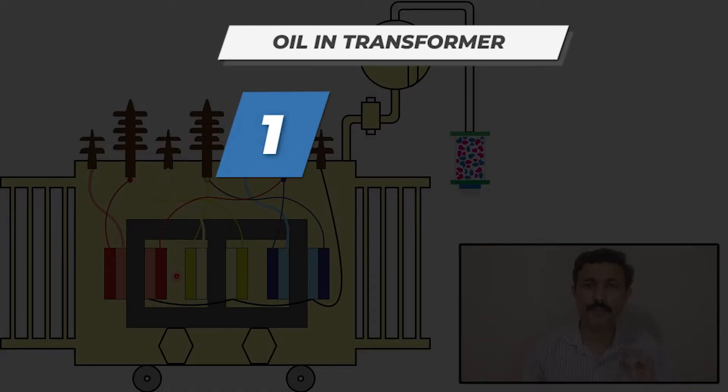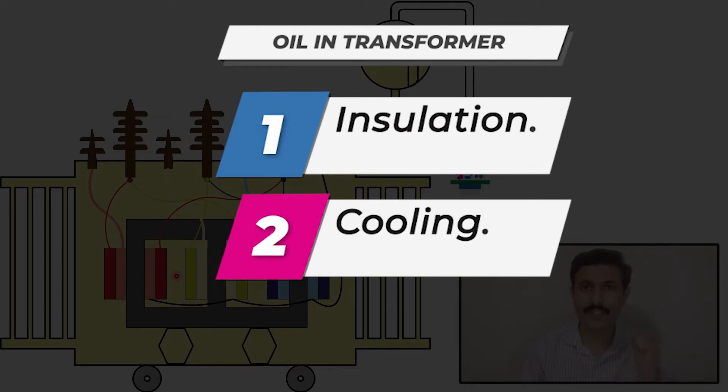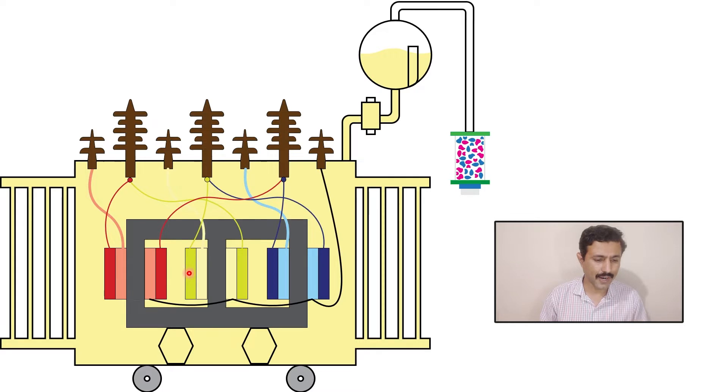The first purpose is to provide insulation and the second purpose is to absorb the heat from the winding. When these windings are heated too much, the oil in the transformer absorbs the heat and tries to cool down the windings. But on the other side, that oil gets heated. When the oil gets heated, its density becomes low.